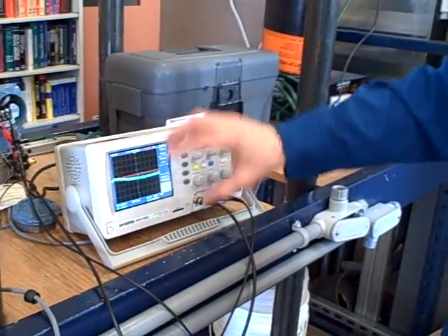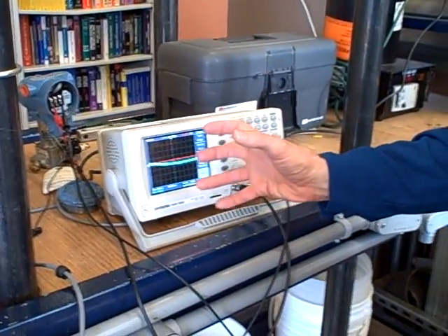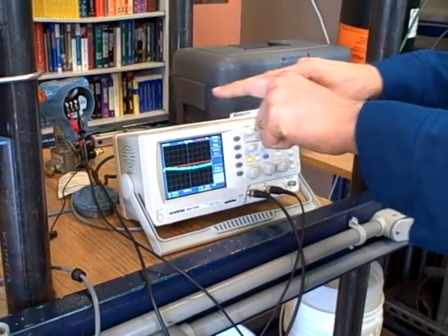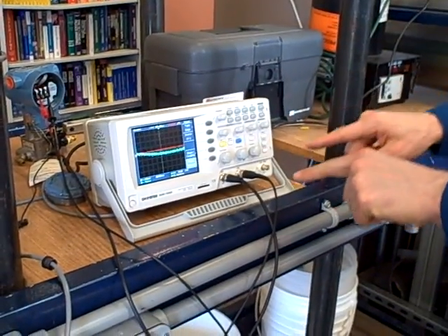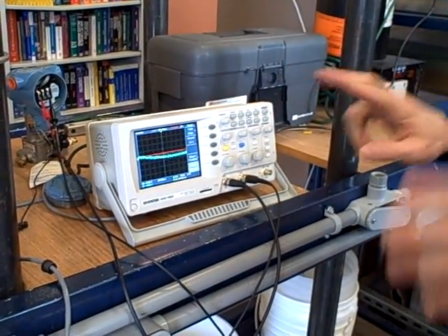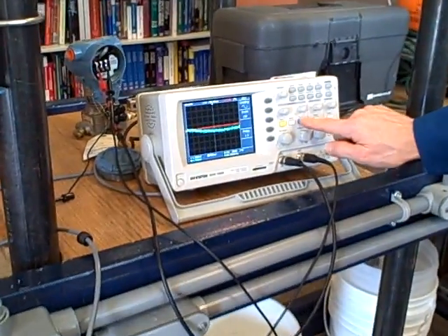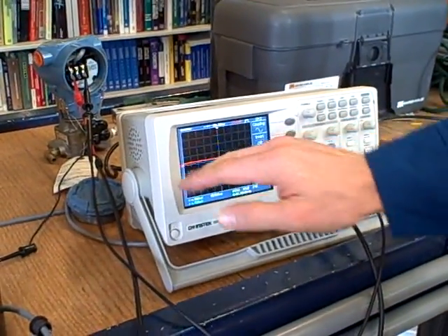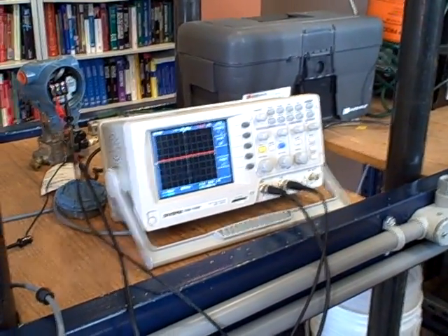This is a very vivid example of how differential signal measurement tends to reject or ignore common-mode noise, because that common-mode noise is introduced on both conductors equally. And if we have 60 Hz noise on both conductors equally, yellow and blue equally going up and down, the difference between them will not see that noise. That's why the red is so nice and straight. What's left is a signal that's nice and straight and practically noise-free, because it's a difference between those two conductors, not ground-referenced.